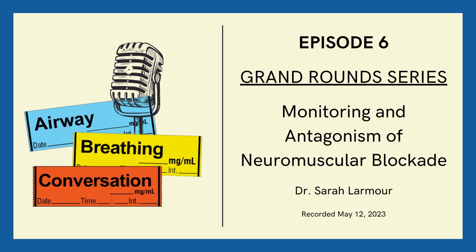But what all of this really led me to ask was, what even is the accuracy and reproducibility of the different types of neuromuscular monitoring devices? And are they interchangeable? As many studies, especially the meta-analysis, combine data from centers using multiple different models and modes of measurement of this train of 4 ratio. So there are three main methods or techniques of quantitative twitch monitoring that we can use: mechanomyography or MMG, accelerometry or AMG, and then electromyography or EMG.